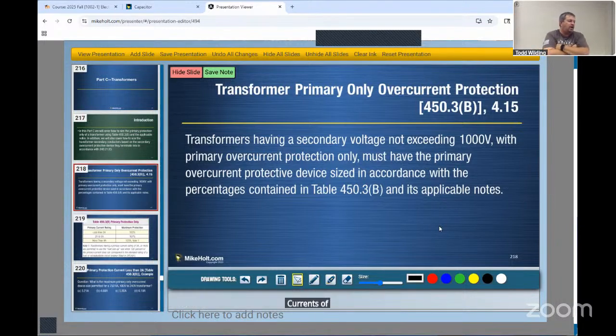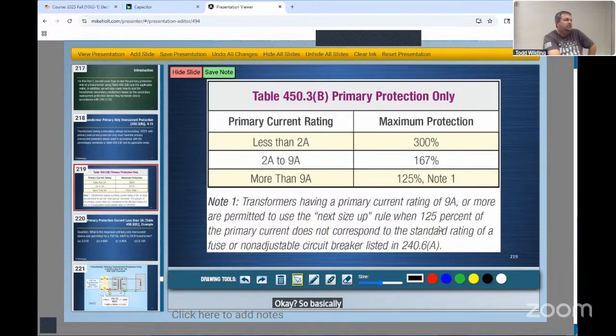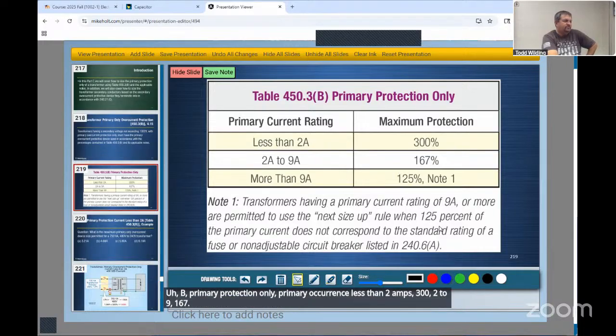Currents of 9 amps or more, I multiply that answer by 125%. Currents less than 9 amps, I multiply my answer by 167%. Currents less than 2 amps, I'm allowed 300%. And then it goes into the secondary protection if I want that. Then there are some footnotes underneath, 1, 2, and 3. So basically, primary protection only: primary currents less than 2 amps, 300; 2 to 9, 167; 9 amps or more, 125.